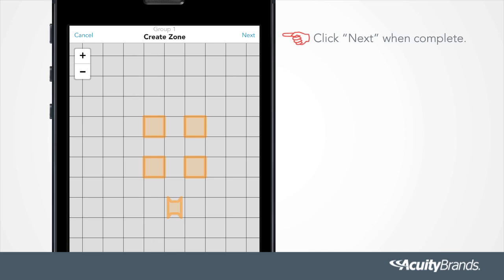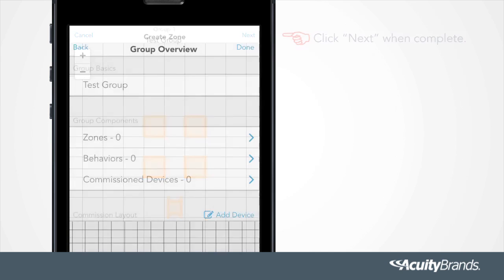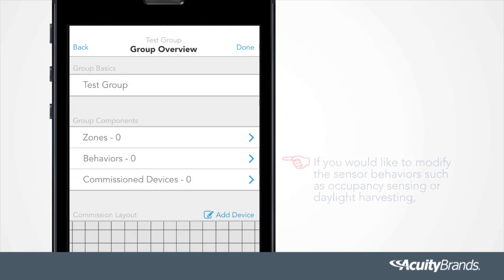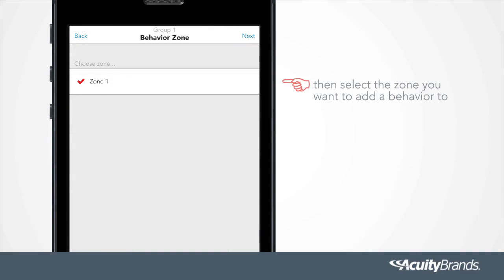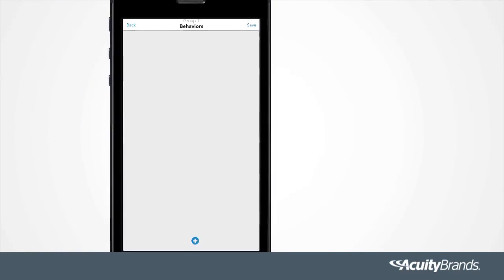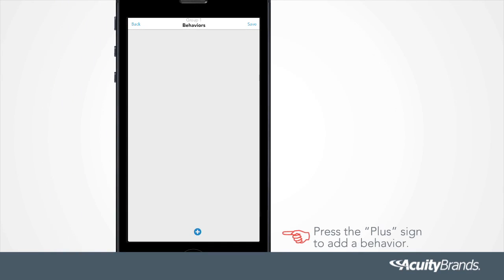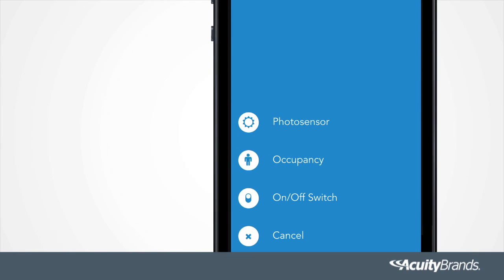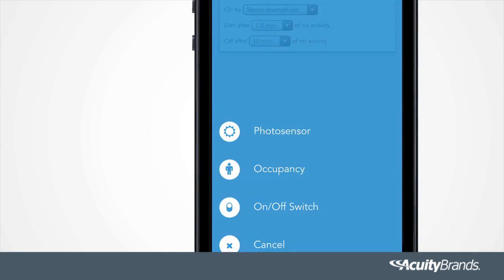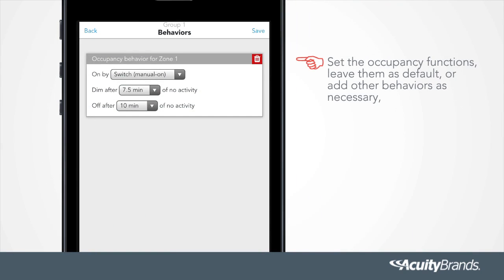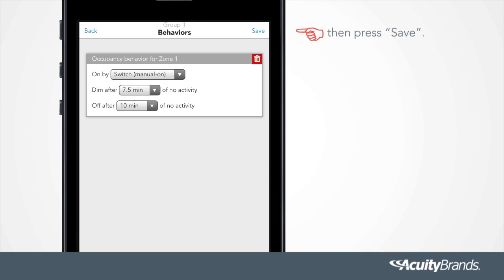Click Next when complete. If you would like to modify the sensor behaviors, such as occupancy sensing or daylight harvesting, then select the zone you want to add the behavior to and press Next. Press the plus sign to add a behavior. Select the behavior you want to add. Select Occupancy. Set the occupancy functions, leave them as default, or add other behaviors as necessary. Then press Save.